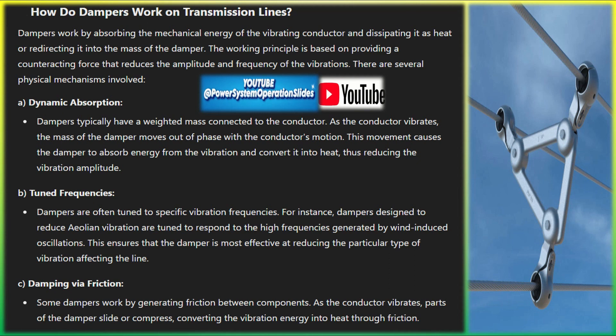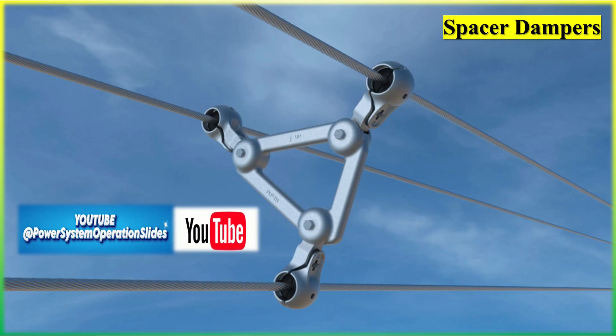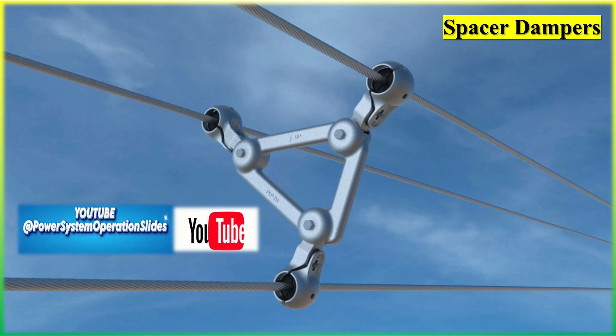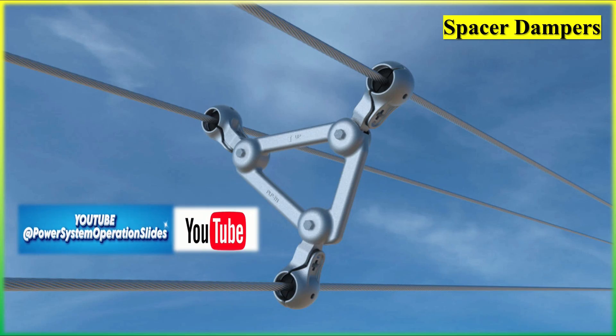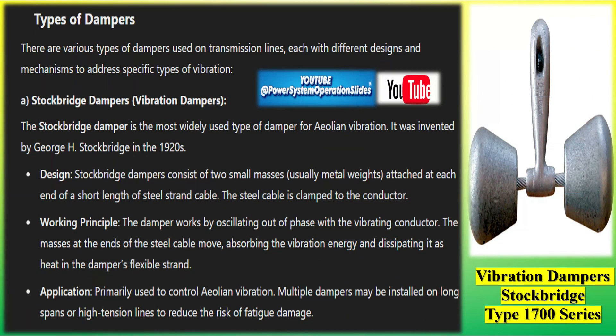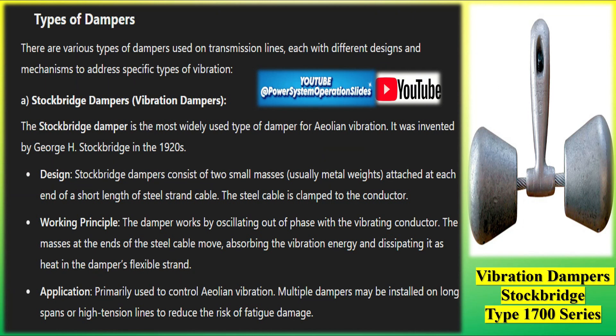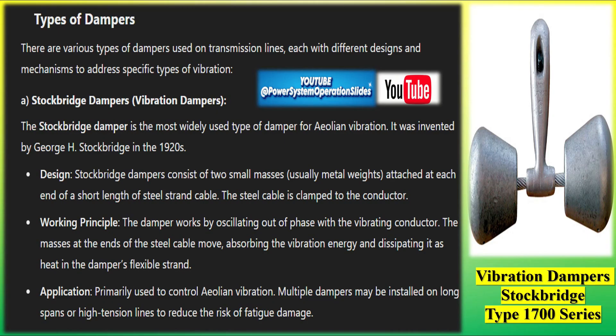The Stockbridge damper is the most widely used type of damper for Aeolian vibration. It was invented by George H. Stockbridge in the 1920s. Stockbridge dampers consist of two small masses — usually metal weights — attached at each end of a short length of steel strand cable, which is clamped to the conductor. The damper works by oscillating out of phase with the vibrating conductor; the masses at the ends of the steel cable move, absorbing the vibration energy and dissipating it as heat in the damper's flexible strand. Multiple dampers may be installed on long spans or high-tension lines to reduce the risk of fatigue damage.